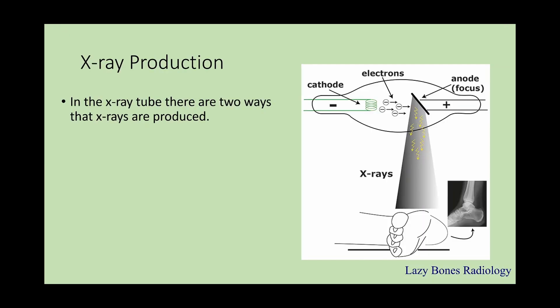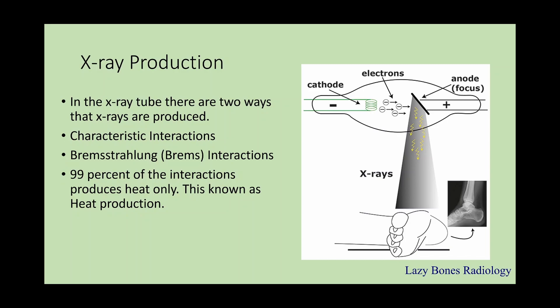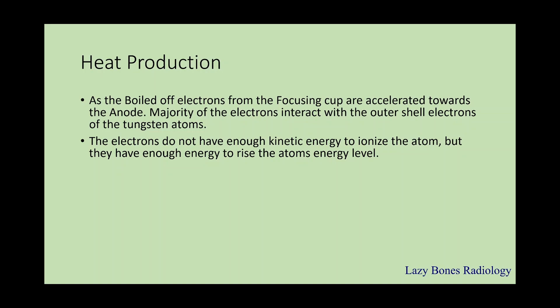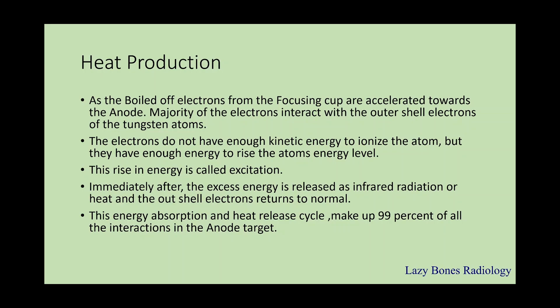This brings us to the x-ray production. In the x-ray tube, there are two ways x-rays are produced: characteristic interactions and Bremsstrahlung interactions. 99% of the interactions only produce heat — this is known as heat production — while only 1% of the interactions result in making x-rays. As the boiled-off electrons from the focusing cup are accelerated towards the anode, the majority of electrons interact with the outer shell electrons of the tungsten atoms. These incoming filament electrons do not have enough kinetic energy to ionize the atom, but they do have enough energy to raise the atom's energy level. This rise of energy is called excitation. Immediately after, the excess energy is released as infrared radiation or heat, and the outer shell electrons return back to normal. No x-rays are produced during heat production, only heat release.